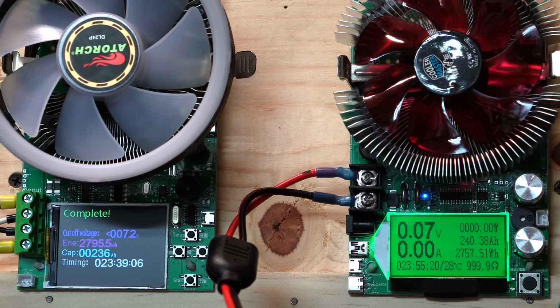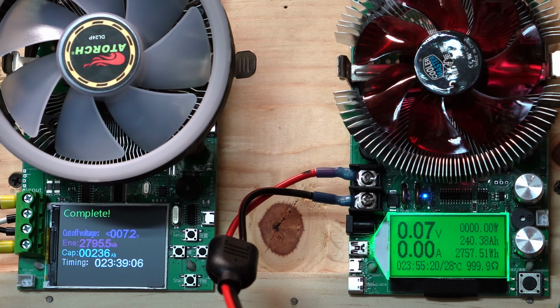Now, I think what's even more noteworthy is if you take a look at the amp hour reading. On the one on the left, it says 236 amp hours, and on the one on the right, 240.38 amp hours. This is a 460 rated amp hour battery, and we got 476 amp hours. You might ask why we get more amp hours but less watt hours. I think the reason is that we're pulling these testers at such a relatively low wattage that this test runs for about 24 hours, so we're losing a little bit of that overall watt hours in the process of that 24-hour discharge.